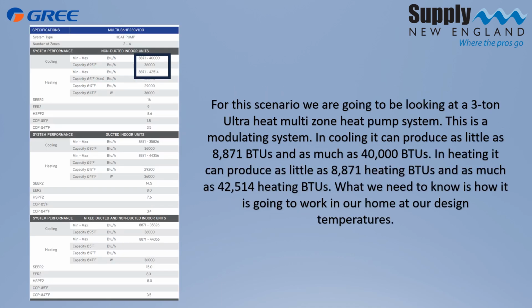For this scenario, we're going to be looking at a 3-ton UltraHeat multi-zone system. This is a modulating system. It will modulate between 8,871 BTUs to 40,000 BTUs in the cooling mode and 8,871 BTUs in the heating mode, all the way up to 42,514.